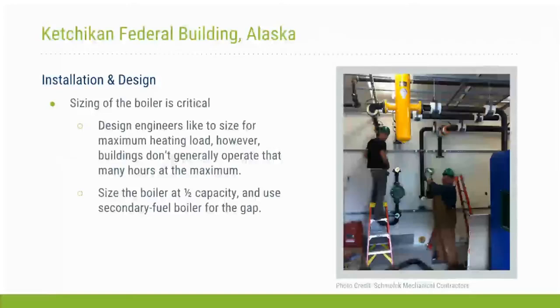Generally, operationally speaking, design engineers, mechanical engineers tend to size mechanical systems based on peak heating or cooling loads. And as we all know, mechanical systems run at peak operation maybe 10% of the annual hours or less. This generally tends to oversize building mechanical systems, and as Greg mentioned in his presentation, that seems to be the same case at Ketchikan as well. The building boiler is not grossly oversized, but it's oversized, and it's impacting its economics and its operation as well.